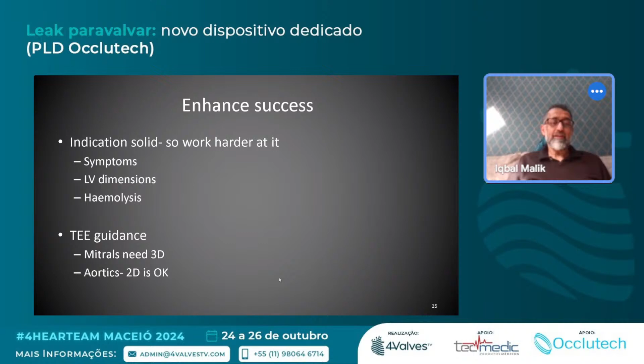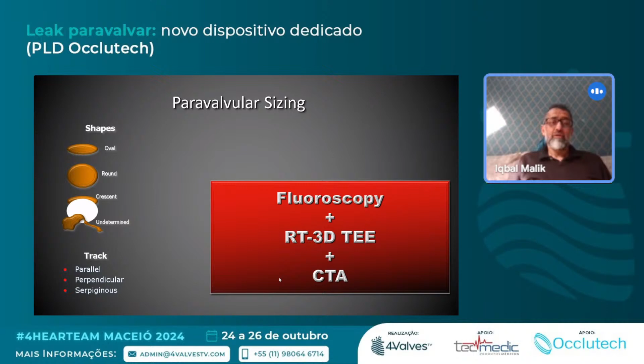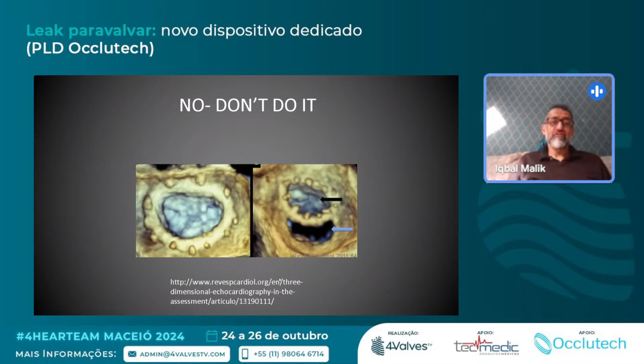I personally have never balloon sized a leak, but I know that some people do. I use the device size that will go through the biggest sheath that will go through the leak without affecting the leaflets. And of course, if the whole valve is falling off, you can't close that with a plug.